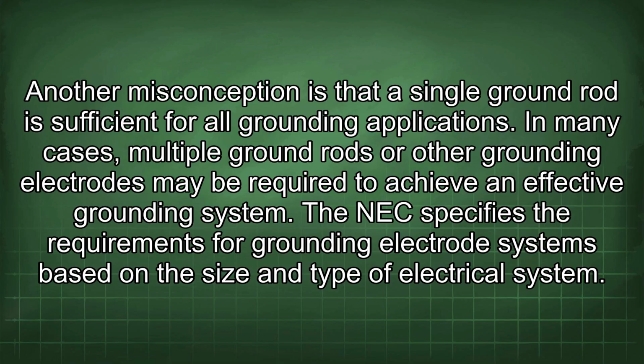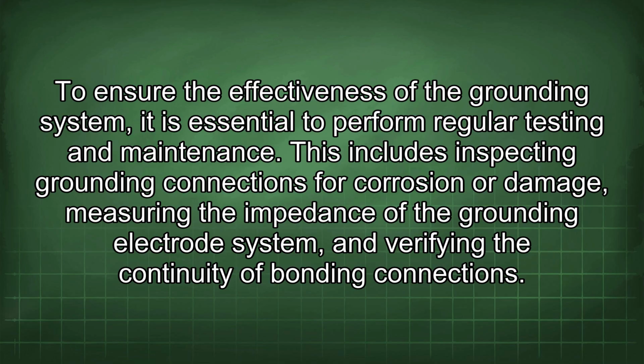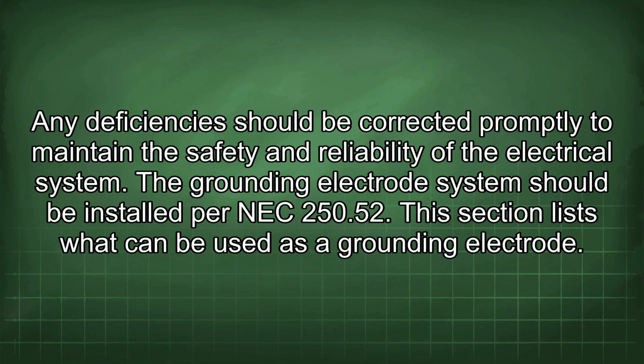In many cases, multiple ground rods or other grounding electrodes may be required to achieve an effective grounding system. The NEC specifies the requirements for grounding electrode systems based on the size and type of electrical system. To ensure the effectiveness of the grounding system, it is essential to perform regular testing and maintenance. This includes inspecting grounding connections for corrosion or damage, measuring the impedance of the grounding electrode system, and verifying the continuity of bonding connections. Any deficiencies should be corrected promptly to maintain the safety and reliability of the electrical system.